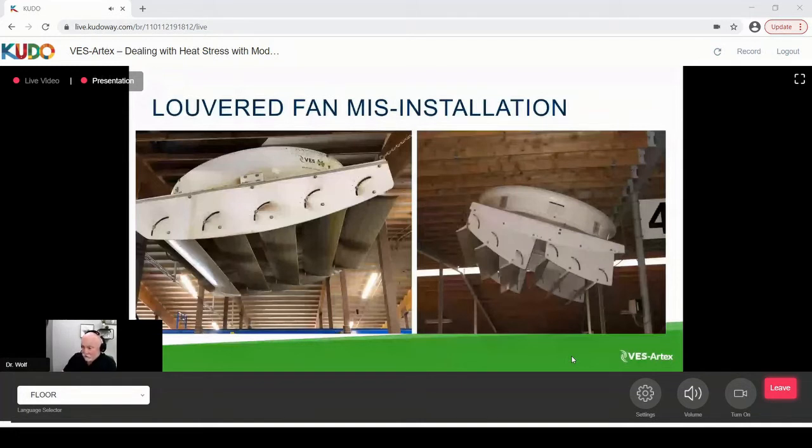The other one, you can see some here in this one, and this one that's a little hard, but these fans are too close to the ceiling. That fan is going to start moving air into that throat about 9 feet out in all areas around us. So anything that restricts that is going to restrict how much air comes out the outtake on this fan. So it's hugely important to be noticing what's restricting that. And again, there's mounting instructions as to what that should be placed at to get the optimal performance out of that fan.